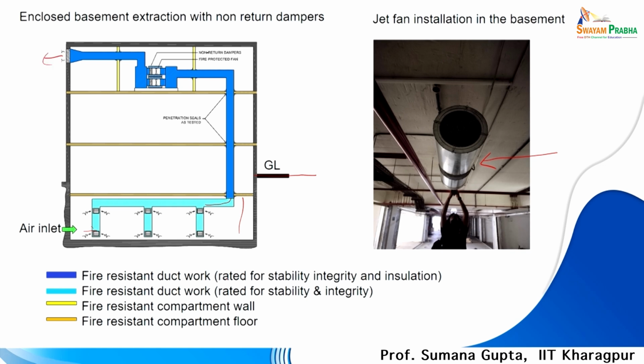So, fire resistant duct rated for stability, integrity and insulation, and fire resistant ductwork rated for stability and integrity, not for insulation, which is in the basement, fire resistant compartment walls. So, these are all fire resistant compartment walls and fire resistant compartment floor. These are compartment walls, and this is the fire resistant compartment floor. So, what is done? Enclosed basement extractor with non-return dampers. So, these are all fixed with dampers, so that no contaminated air or smoke-infiltrated air can return back to these zones, and the outlet is outside the building.